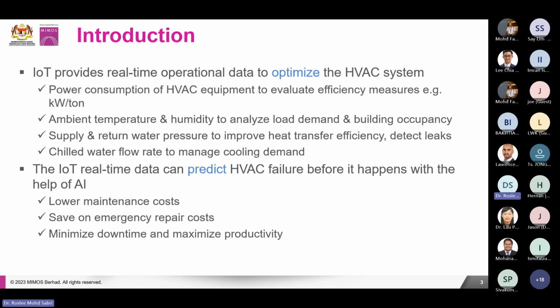For example, if we could measure the power consumption of all the equipment, we can evaluate how efficiently this equipment is running, using metrics like kilowatt per ton or some efficiency ratio calculation. We could track over time how efficient the equipment is running, and if the efficiency drops, that could trigger us to do maintenance and find out if there are problems with the machine.